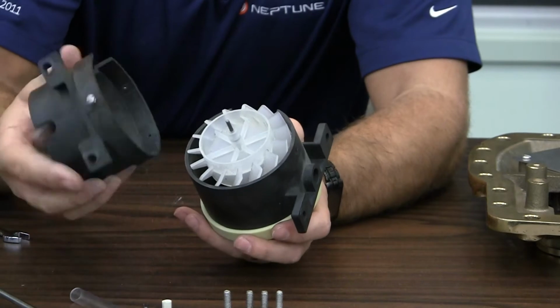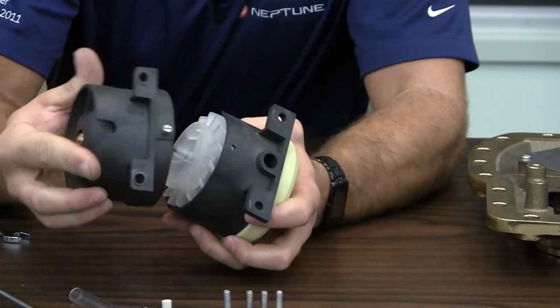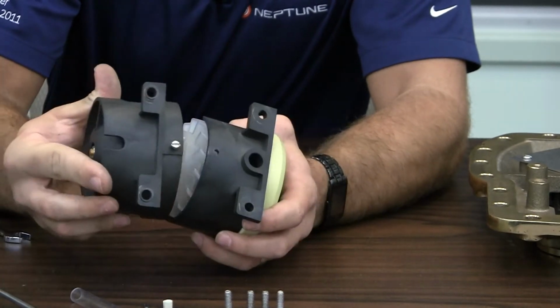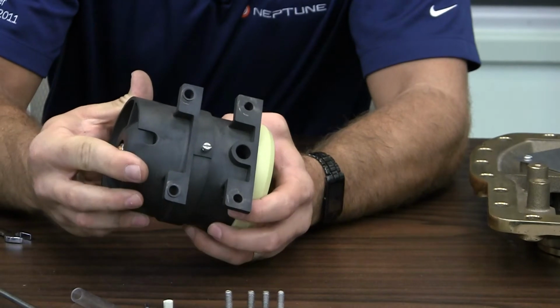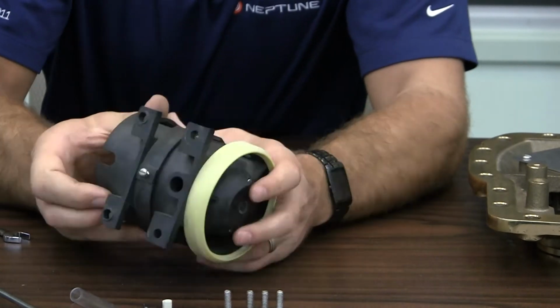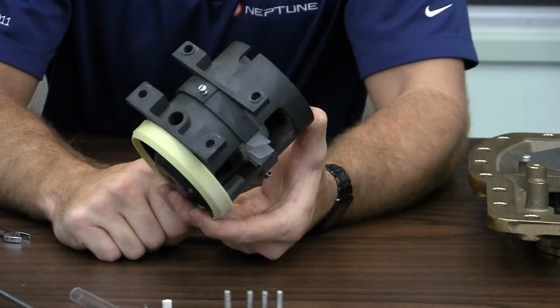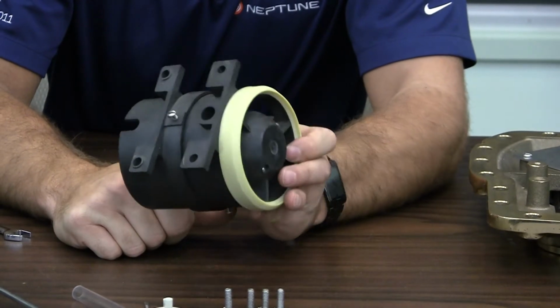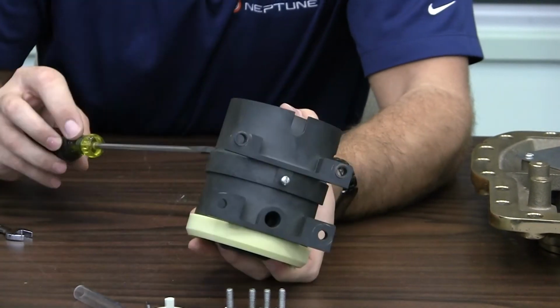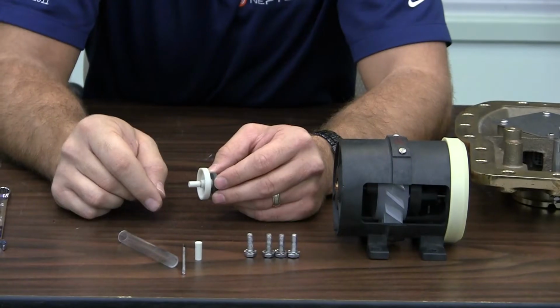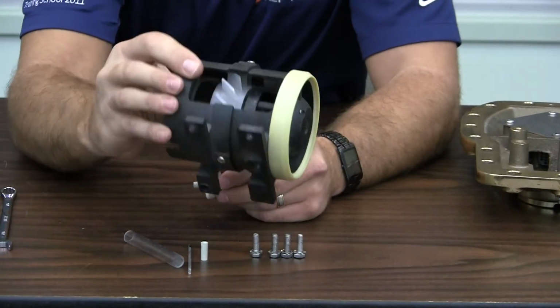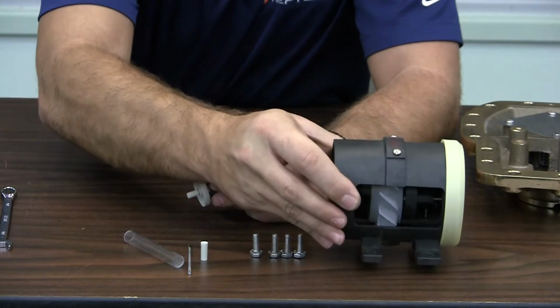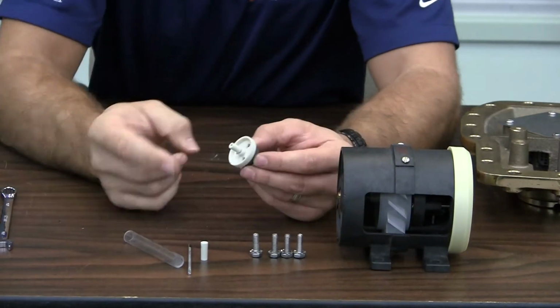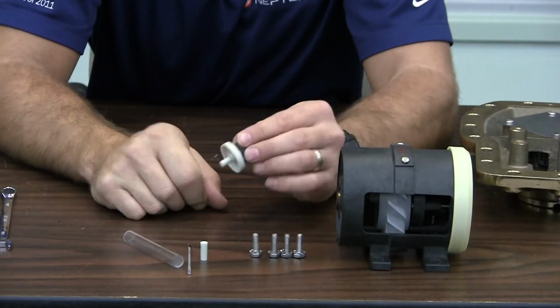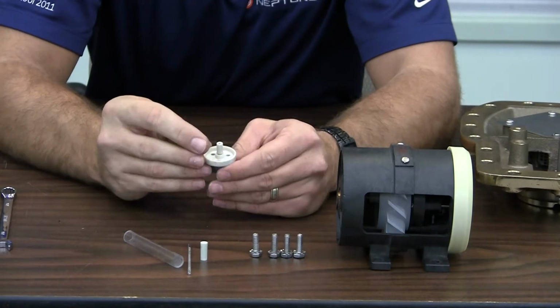and then take the inlet side of the turbine assembly and place it back. There's a mating hole for that shaft to fit into. And then we'll tighten our 3 screws back to hold the assembly complete. We have tightened 3 screws on the turbine assembly, and it's now back together. Before we can put the turbine back in, we have to recomplete the magnet drive. I've got the magnet assembly in my hand.